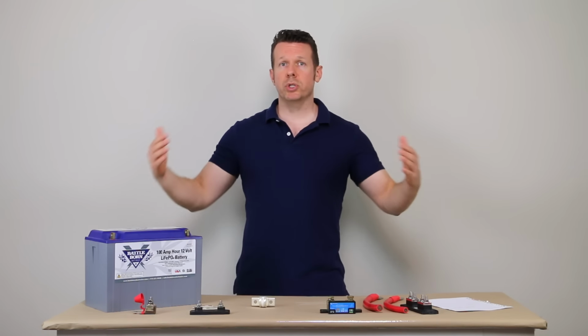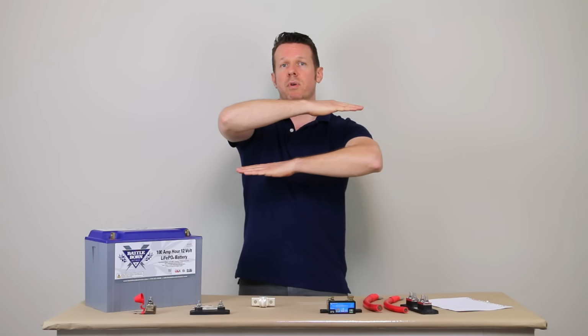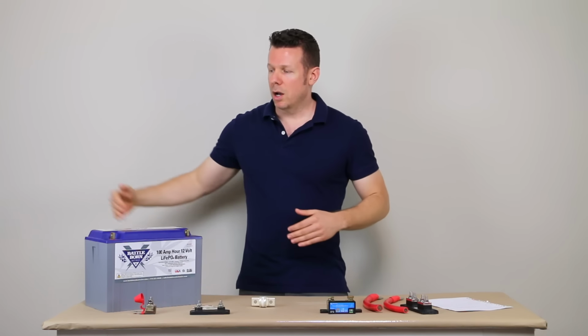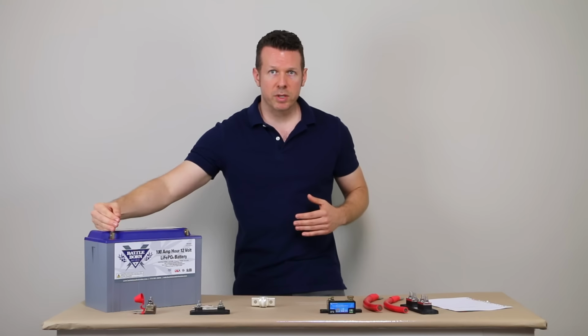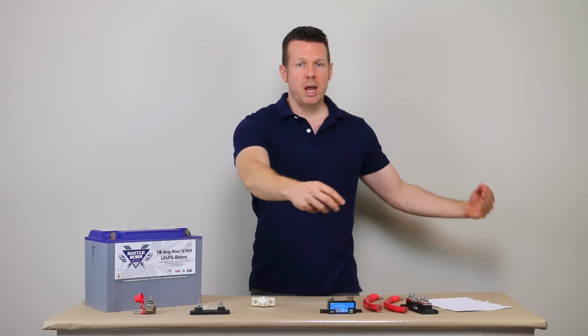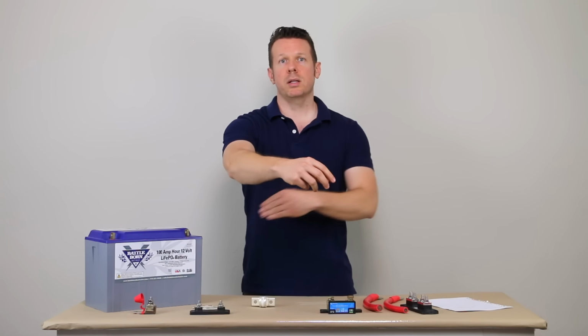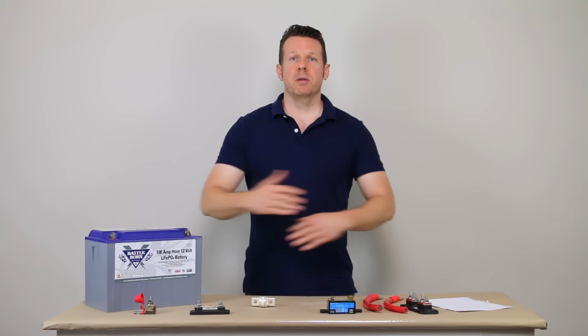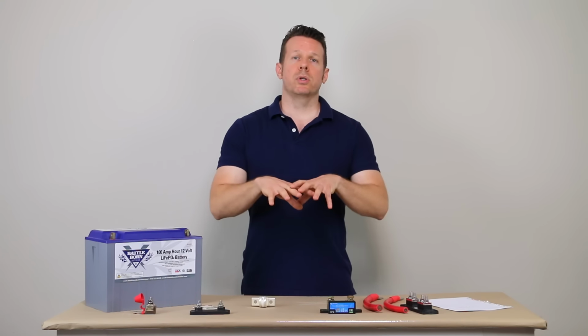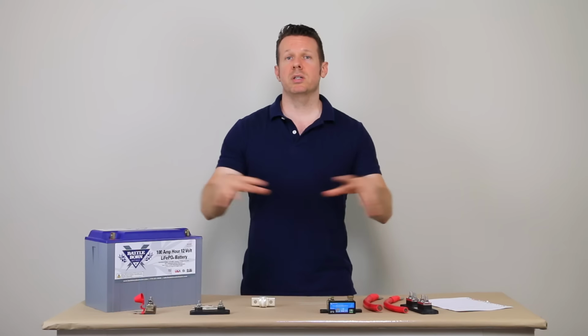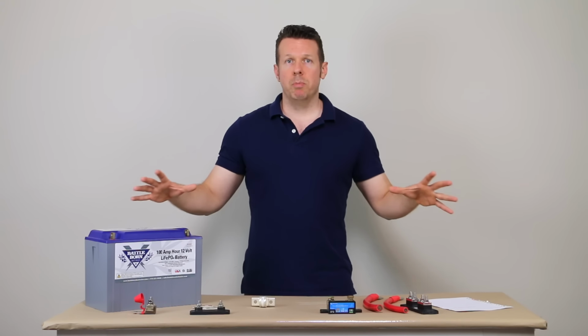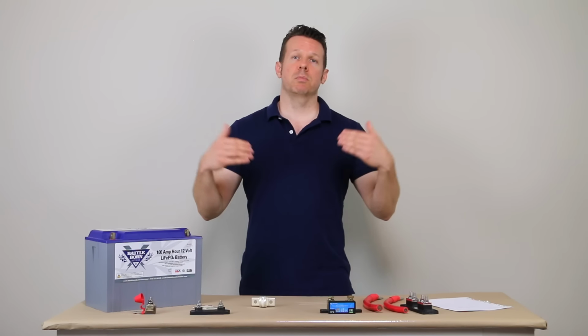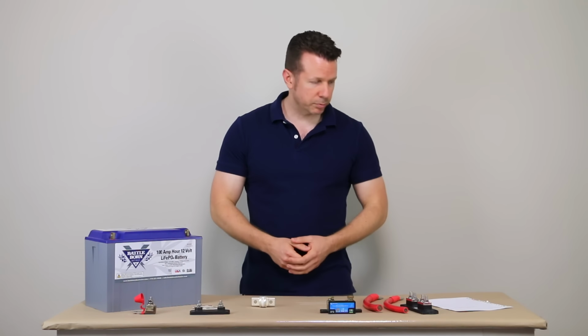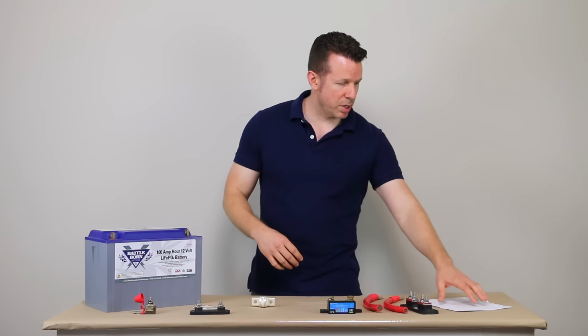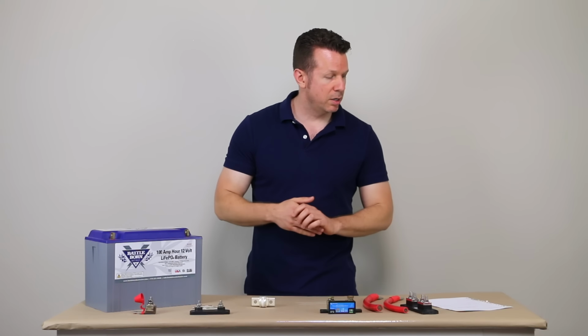So what you want to do is bring positive and negative in from opposite sides. Your positive can come in on this side and link down. Your negative can come in this side and link down as well. And that's going to balance out the voltage drop, and it's going to balance out the charging and discharging amongst all the batteries so that they age consistently together. So that is mistake number 3, having a battery at the end of the line.